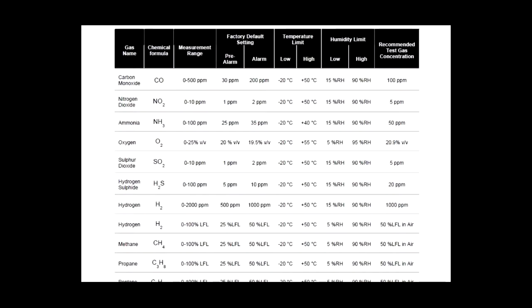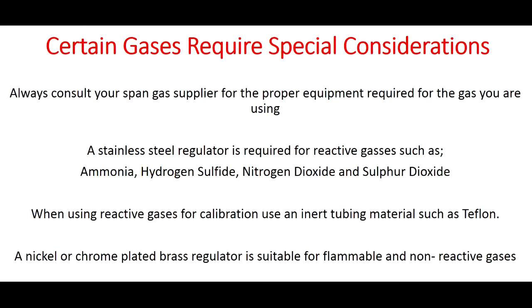To choose the proper span gas concentration, please refer to the ECO Product Guide, Appendix A. Note, toxic gases are referred to in parts per million, and flammable gases are referred to in percent lower flammable limit. Certain gases require special considerations. Always consult your span gas supplier for the proper equipment required for the gas you are using.